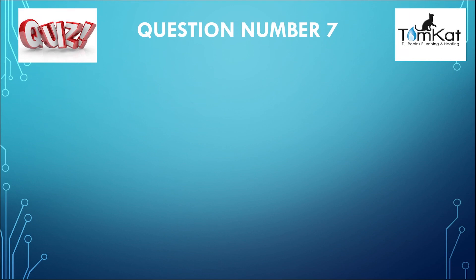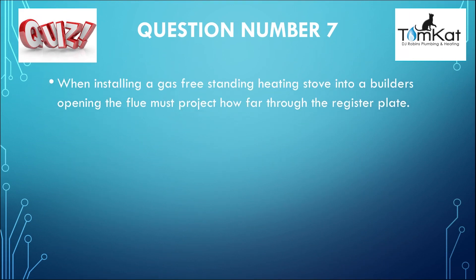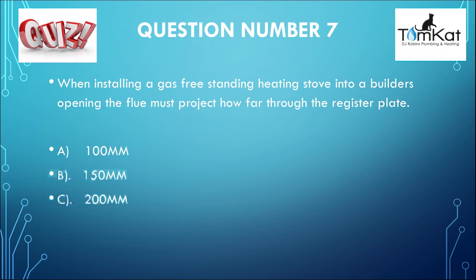Question number seven: When installing a gas freestanding heating stove into a builder's opening, the flue must project how far through the register plate? Is it A, 100 millimetres? Is it B, 150 millimetres? Or finally, is it C, 200 millimetres? That is the end of question number seven.